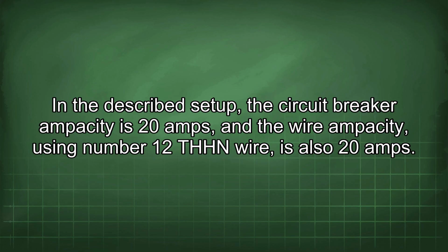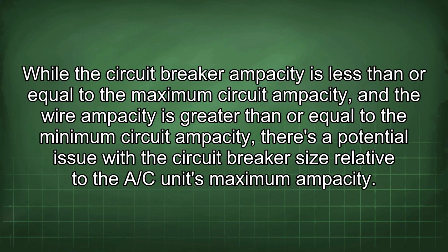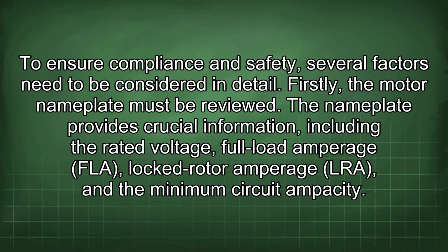In the described setup, the circuit breaker ampacity is 20 amps, and the wire ampacity, using number 12 THHN wire, is also 20 amps. While the circuit breaker ampacity is less than or equal to the maximum circuit ampacity, and the wire ampacity is greater than or equal to the minimum circuit ampacity, there's a potential issue with the circuit breaker size relative to the A/C unit's maximum ampacity. To ensure compliance and safety, several factors need to be considered in detail.